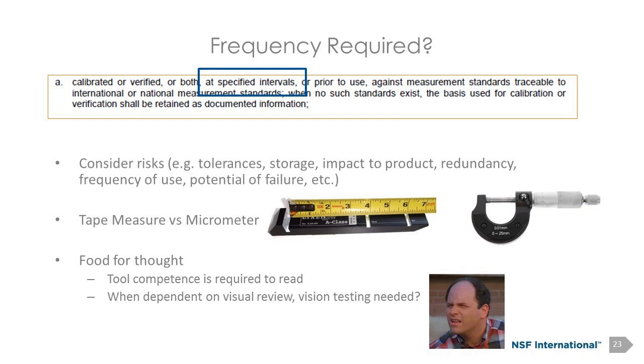As for the frequency required, the standard, again, doesn't tell us shall be annually, shall be semi-annually. It says at specified intervals. So it's going to be a business decision for each company, and we're going to consider the complexity of our product, the tolerances that we're measuring, the storage conditions for our product, the redundancy of the inspections that are being performed, the frequency of that tool being utilized, maybe the potentials for failure, measurement error, stuff like that. We're going to consider all of the risks associated with the tool, and we're going to determine how often that tool needs to be reconfirmed or reaffirmed as being good, as being valid.